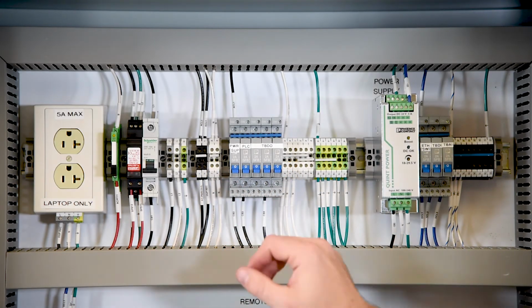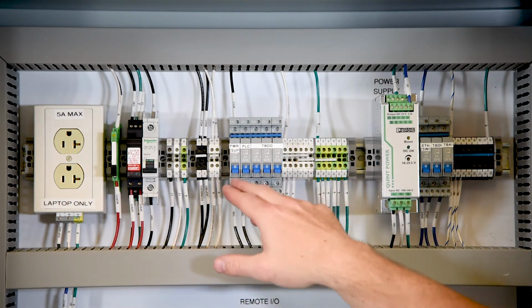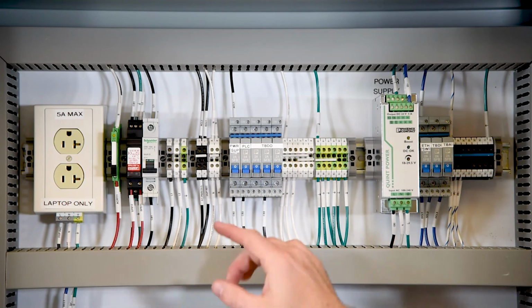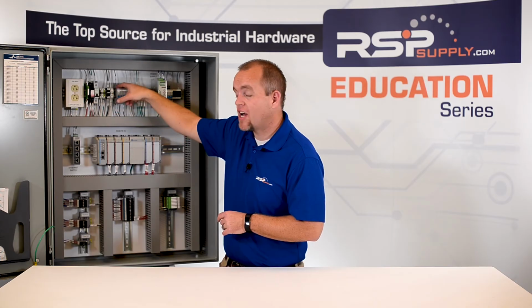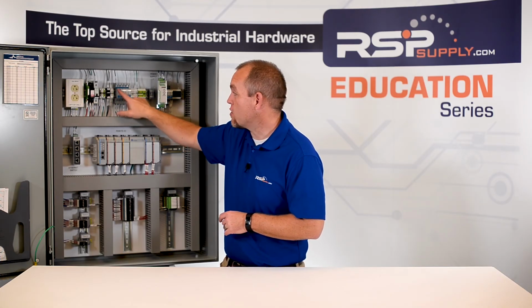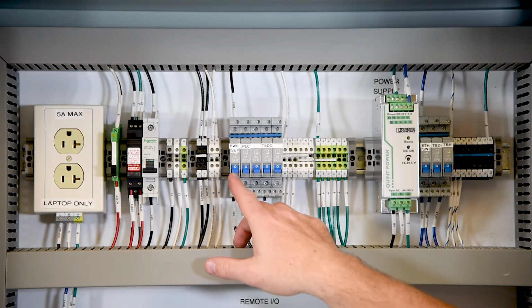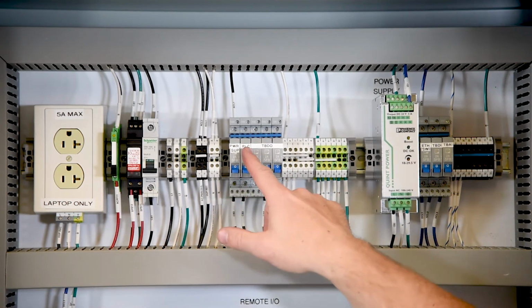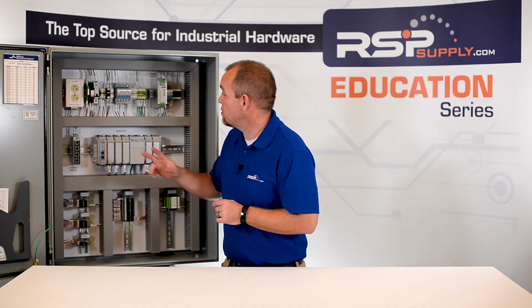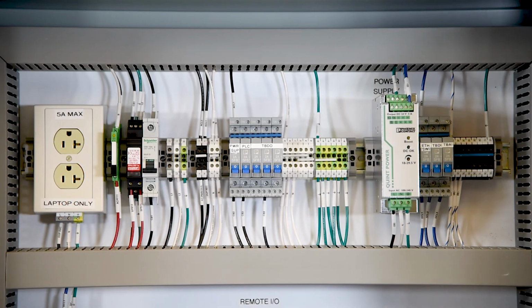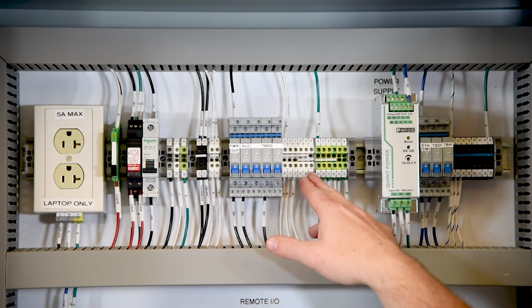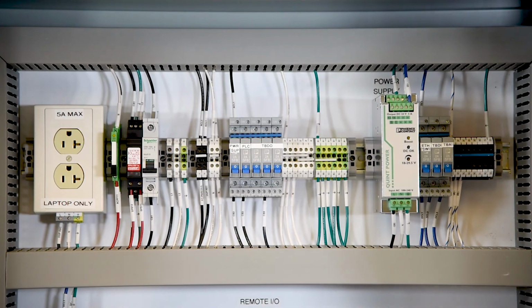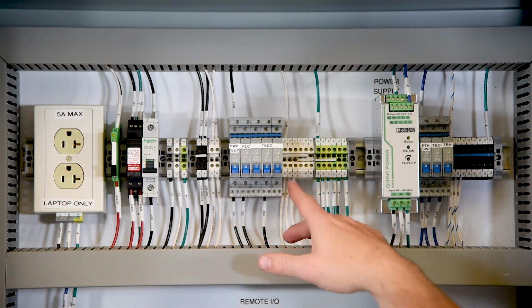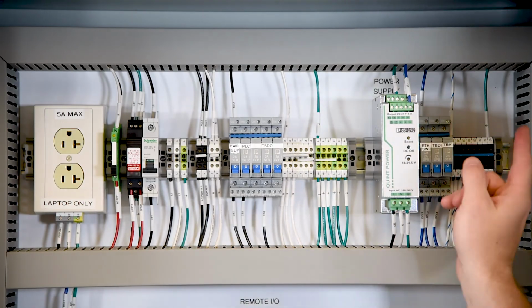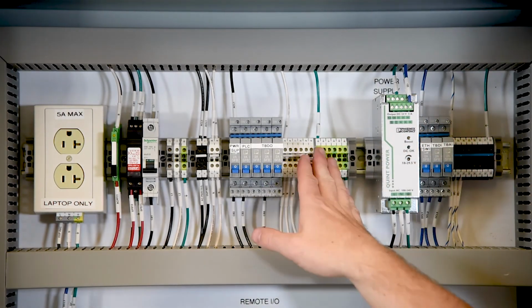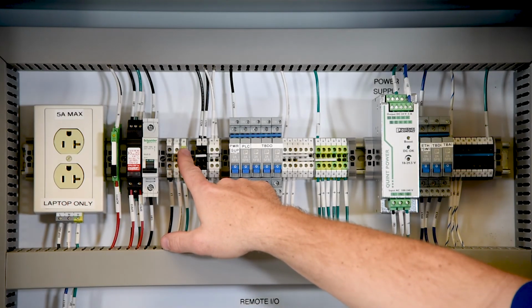In this case, these breakers are going to supply power to all the devices within this industrial control panel. The power comes in on this main wire. All the breakers are tied together with a jumper bar, and then power is individually distributed to each device. In this case, we have power going to the power supply, our PLC, so on and so forth. You can also see here in our AC power distribution, we have our neutral bus, which ties neutral to all AC power devices, as well as our main grounding bus. All grounding comes to this bus, as well as ground from our DC negative. This ties directly to our main input power and the main grounding wire.